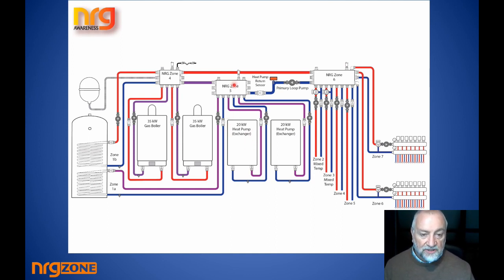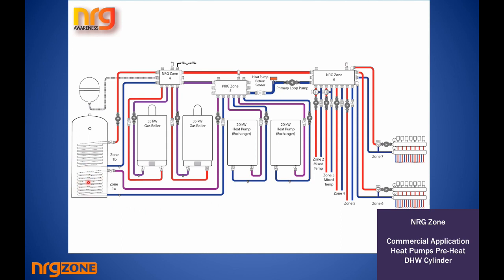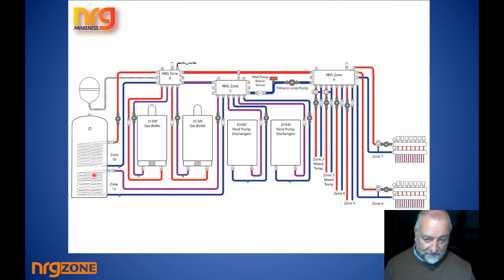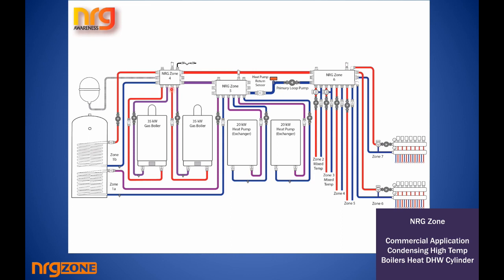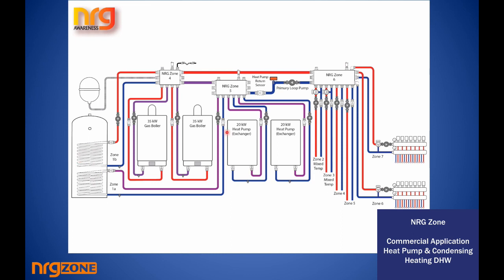If I have two heat pumps and I want them to be able to heat a low temperature coil in a cylinder for preheating purposes, if this boiler is underneath, you remember what we said a while ago, they can draw water from the cold chamber and put it into the top chamber, and this pipe here, A1 and A2, that's connected to the top chamber, so that can take the heat down and it can heat the cylinder. So the heat pumps just on their own can operate away and heat the cylinder, if you have night rate electricity or whatever, to preheat your calorifier, whatever size calorifier you might have. At the same time, if the gas boilers decide you want a full temperature, they do exactly the same thing. They take the heat from the cold chamber, push it up to the top chamber, and this pump takes it down and heats the high temperature hot water. So if you use this system, you can have preheating and high temperature, where the gas boilers can modulate.